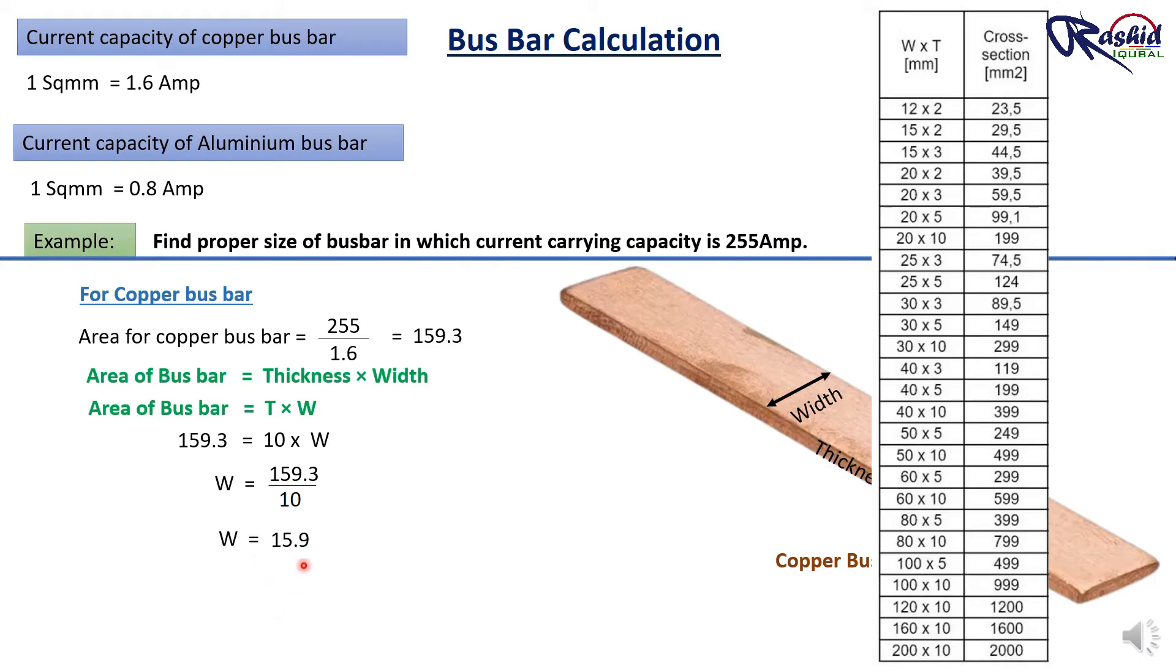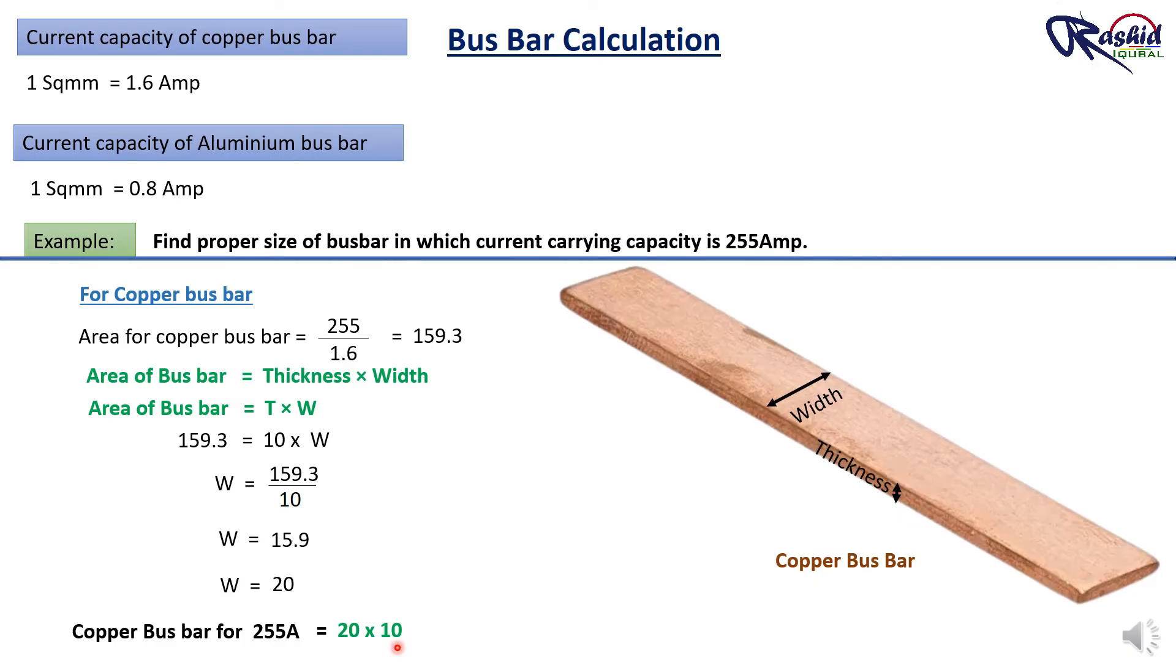Since 15.9 mm is not a standard size, so we can choose the next bigger width available in the market, which is 20 mm with 10 mm thickness. Therefore, the selected size of copper busbar is 20 mm by 10 mm, which is capable of carrying the required 255 ampere current. So here we can use 20 by 10 mm of copper busbar.